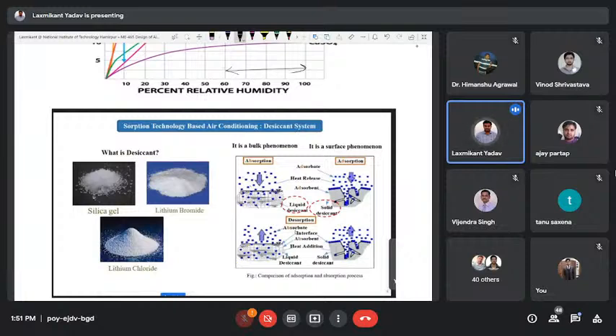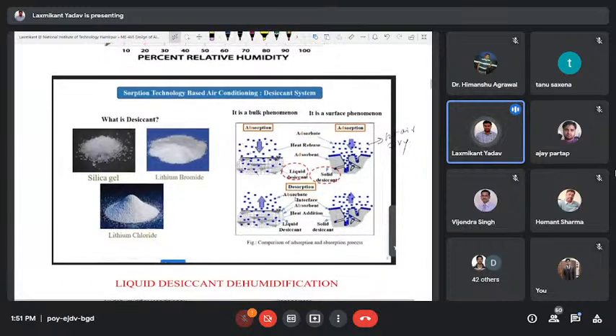This capillary condensation is different from other condensation. Basically, condensation takes place at the saturation pressure, but in capillary condensation, the condensation takes place before the saturation pressure. Because of the confined space, the interaction between the molecules is very low, so there will be capillary condensation, and due to that condensation heat is released, and that heat raises the temperature of the desiccant material as well as the air. Therefore we get hot air, but it is dry. Okay, so this is one of the key features of the solid desiccant. Similarly, in a liquid desiccant solution, we already studied the vapor absorption system. In a vapor absorption system there is an absorber, and in the absorber there is heat release, so that heat is compensated by the cooling water.